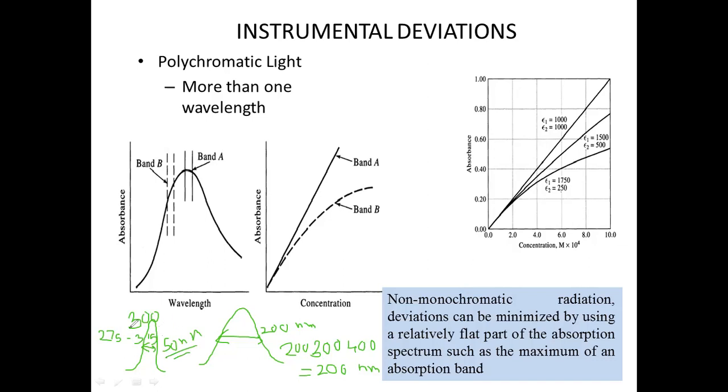So here the monochromator is working more precisely in comparison to this case, wherein the band pass or non-monochromaticity is observed. More non-monochromaticity is observed in this particular case. So generally, the monochromator performance is dependent upon the band pass. The narrower the band pass, the more monochromatic radiation is achieved using a given wavelength selector.